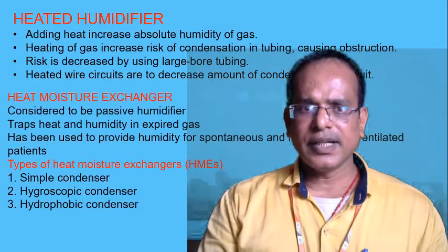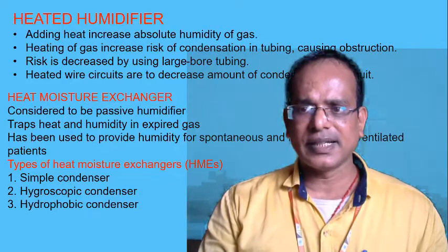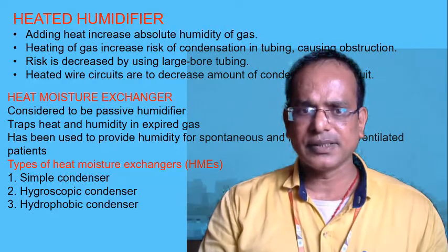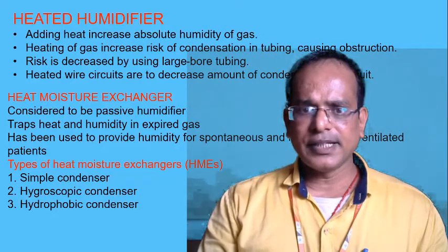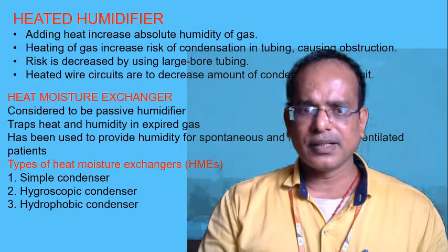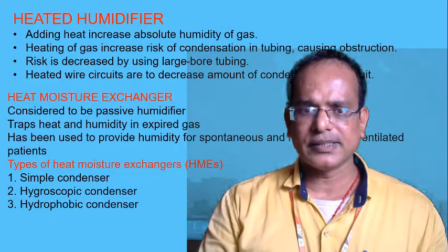Heat moisture exchanger, considered to be the passive humidifier, traps the heat and humidity in the expired gas. It has been used to provide humidity for spontaneous and mechanically ventilated patients. Types of heat moisture exchanger, HME, are: simple condenser, second one is hygroscopic condenser, third one is hydrophobic condenser.